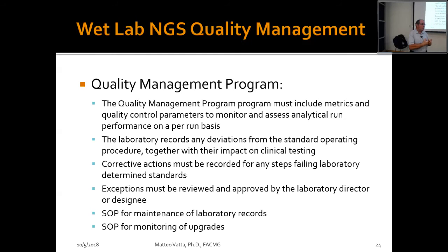Sometimes you can have a better alignment or better clustering, everything. But you have to prove that it is at least as good as the previous one, so you have to do a revalidation of the system, and then everything has to be documented, approved by the lab director, and presented to CAP, because CAP or CLIA need to know that some changes have been put in place, what changes, and what they're expecting. Usually, if this change occurs in the year of the inspection, this will be one thing that the inspectors will look into. So the validation binders.